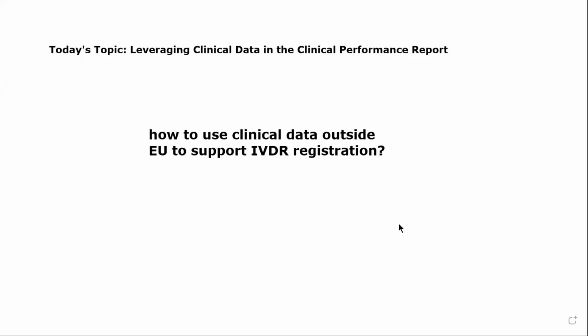Our next question is, how do you use clinical data outside of the EU to support IVDR registration? This is something that we also hear quite a bit, this question. You can certainly use clinical data sets that are derived from studies in the US or all over the world. Global data is definitely allowed.